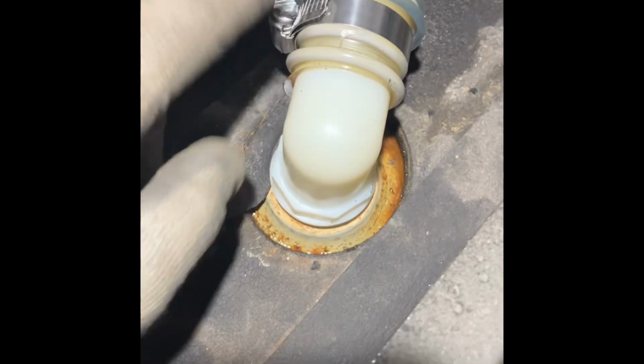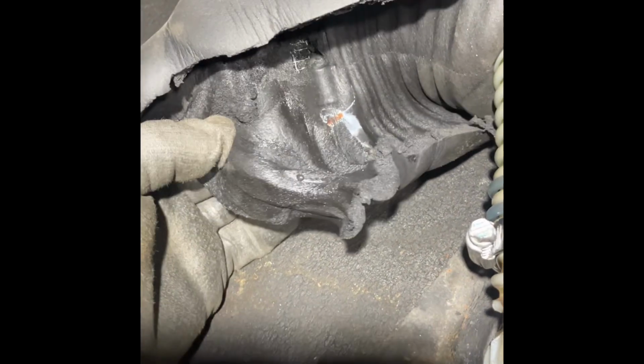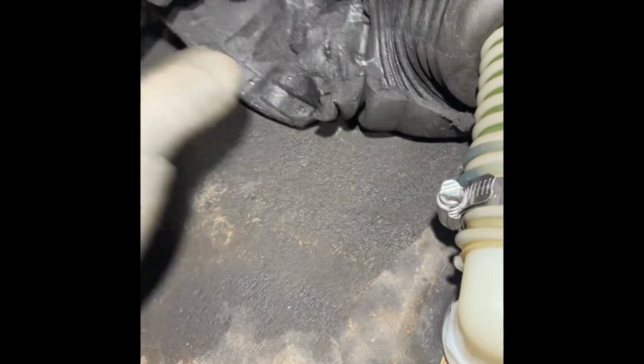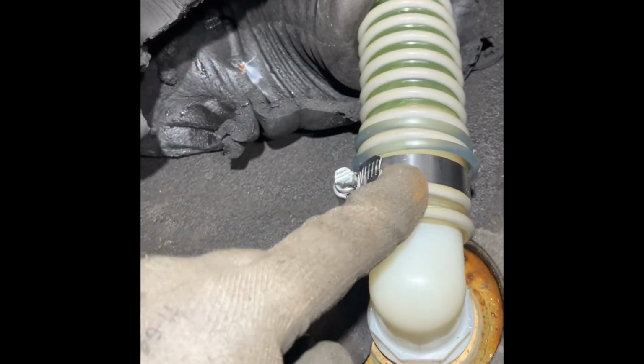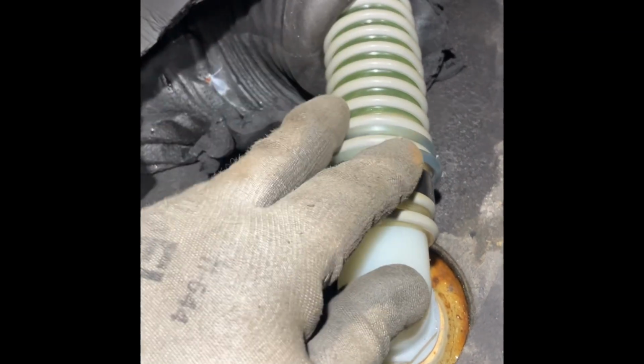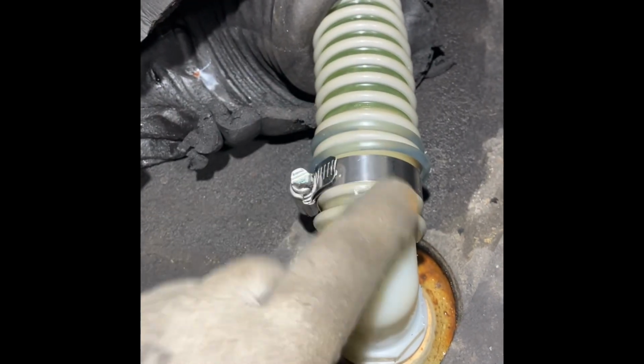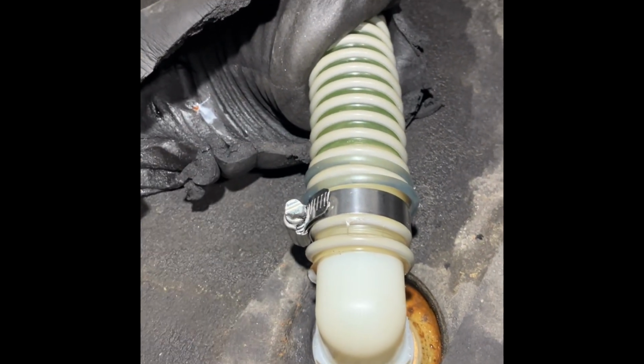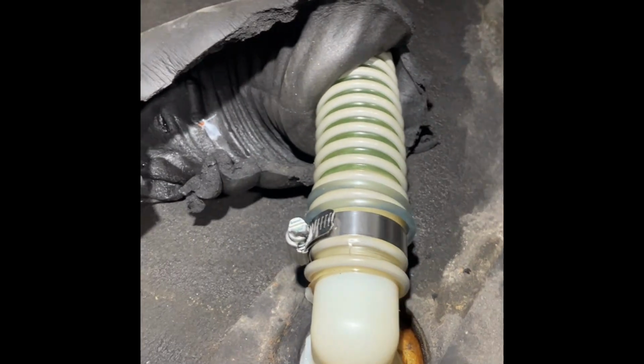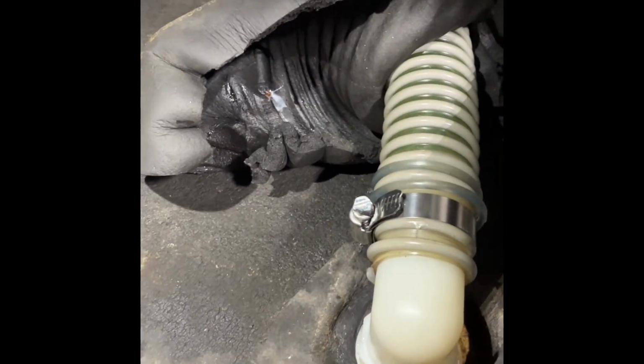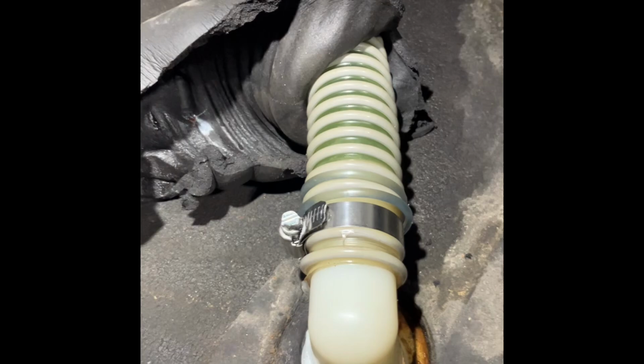I did find right here on top of the glycol storage tank, you can see that's all wet. I did find this hose clamp was a little bit loose. I don't know how well that's showing up on camera, but you can see that the insulation that was over that is all wet. So I snugged that up, and I'm going to leave this off until we get this dryer running again, and then see if that leak went away. The fortunate and unfortunate thing about glycol is that it dries super quick.